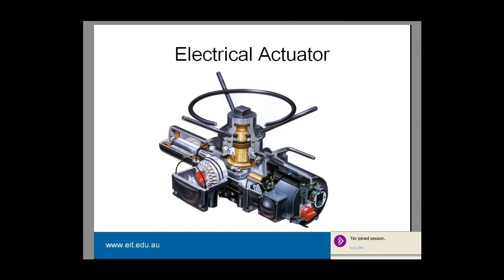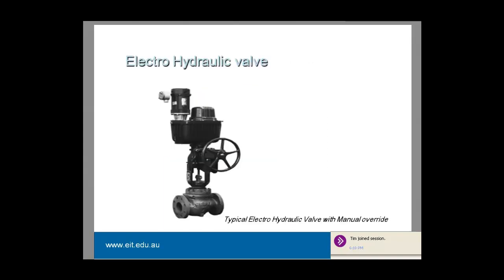We've covered pneumatic and electric. The remaining type is hydraulic actuators. Hydraulic actuators give a fast action and are very suitable for remote areas. They do have a fail-safe action, especially with an accumulator. They're very small and powerful, but quite expensive. Positioners aren't always readily available, and maintenance is generally much more difficult than with pneumatic actuators. You also need to send your working staff on very specialized training courses.